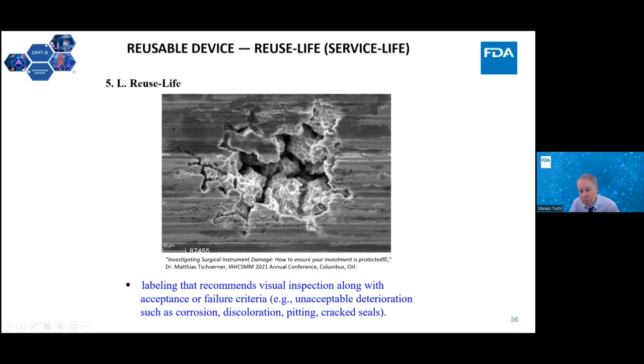And one of our mantras, again, for the reviews we conduct is if you can't clean it, you can't sterilize it. So in other words, if you have a problem feature like this and you get soil buildup in here and you get microbes in here, that soil may shield the microbes from the sterilant, or, depending upon the sterilant, it may actually directly inactivate the sterilant. So things can go wrong from a microbiology point of view, but from an engineering and performance point of view, the performance of this device, this is the beginning of the end. You know, you're going to start having problems.